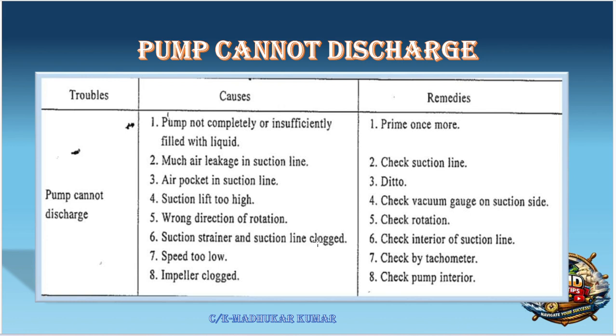Suction strainer and suction line clogged. Yes, it is also possible. So make sure that the suction filter is clean. And if not, then isolate the filter and do the cleaning. Okay. Speed too low. Yes, that means check with the tachometer. The speed is too low. Why is that? The voltage is not supplied, or some electrical problem, some mechanical problem that has to be checked. Impeller clogged. Okay, so in that case, we have to open it and do the mechanical cleaning, complete overhauling, and check the interior part of the pump.